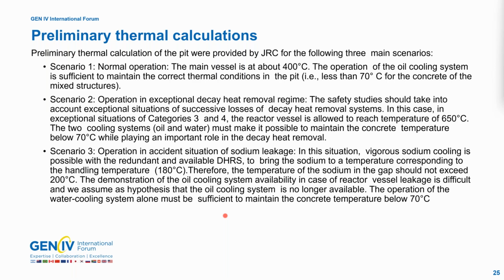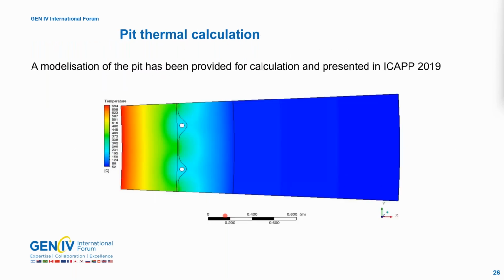And scenario 3 is the operation in an accident situation of sodium leakage. In this situation, we don't even try to demonstrate that the oil system can operate. We say that we lose the oil system, and we demonstrate that the operation of the water cooling system alone is sufficient to maintain the concrete temperature below 70 degrees. Next slide, please. This slide is a view of the modelization that has been provided for the calculation. These calculations have been presented at ICAPP 2019. A paper is available on the subject. Next slide, please.